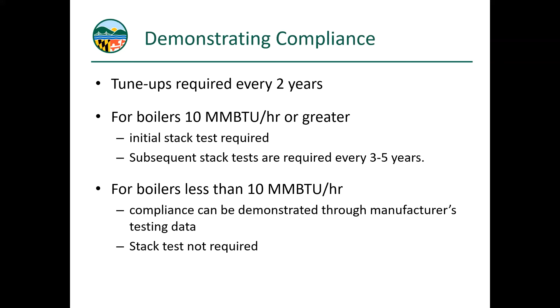For boilers less than 10 million BTU per hour, we will accept compliance demonstrated through manufacturer's testing data. There's an EPA protocol that basically says this model unit has been tested and this is the emissions it's guaranteed to meet. If that meets our standard, nothing else is required for demonstrating compliance with the particulate matter standard.